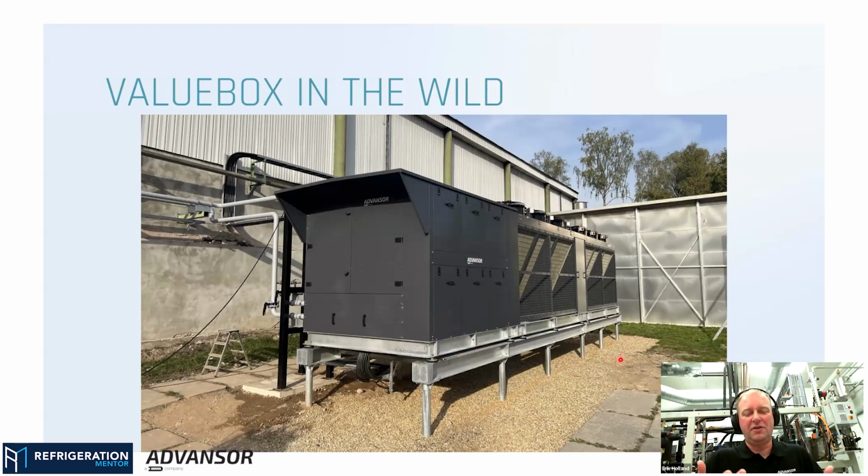So we have to lift it quite a bit to have access to fresh air at all times. And all of this is also stuck in a French drain underneath here to drain away all the water when you're defrosting the system, because as we talked about before, these are evaporators, and like every evaporator, they need to be defrosted from time to time. And there's only one way that water can go, that's down. And if you just have it on a concrete slab or something, you have water everywhere. So you need some kind of drainage.